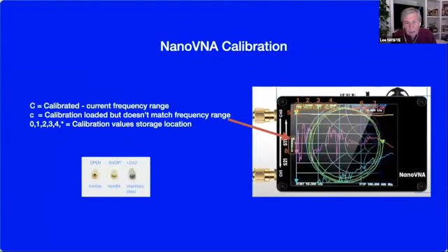Here's the calibration, and I'll just spend a quick second on this. If you look at the red arrow in the middle, it's pointing to a C. And if it's a capital C, that means you're operating in a calibrated domain, frequency range, whatever. And you don't have to recalibrate. But if the C is small, you're outside the calibration range that you can depend on for the ultimate in precision. To be honest with you, I've never really felt in trouble switching back and forth and didn't feel like I had to recalibrate, because you go through the step of you have to put on an open, a short, a load, and have the machine reset itself.